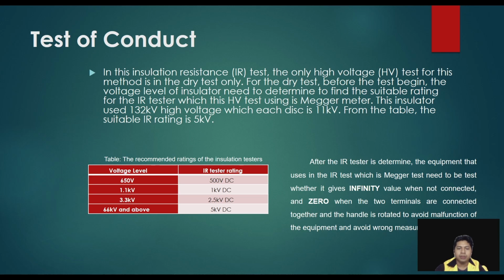So from the table, we can see for the voltage level of 650 volt, the IR testing rating is 500 volt DC. For 1.1 kV, the IR testing is 1 kV DC. For 3.3 kV, the IR tester rating is 2.5 kV DC. Lastly, for 66 kV and above, the IR tester rating we use is 5 kV DC.